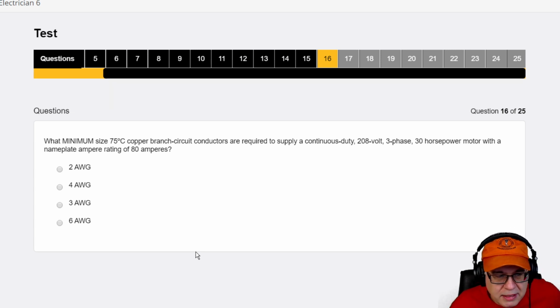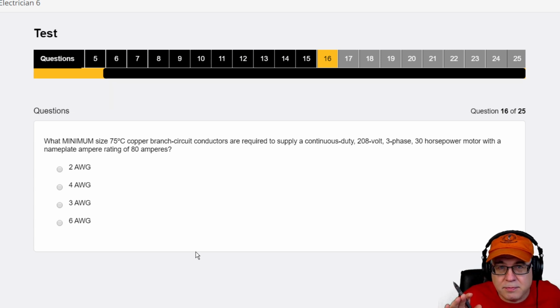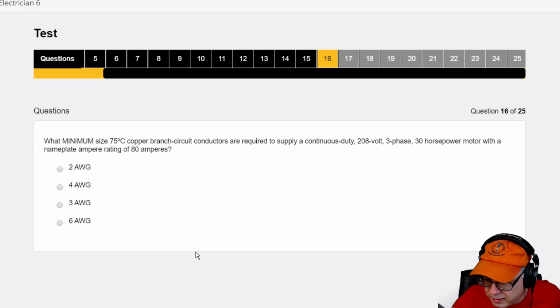Honestly, that nameplate rating of 80 amps doesn't mean anything to me. If you immediately started looking at 80 amps under 310.15(B)(16), you already messed up, because we don't use nameplate amps when sizing conductors. That's only for the nameplate.